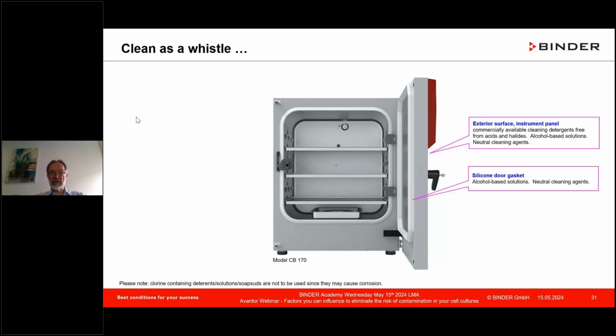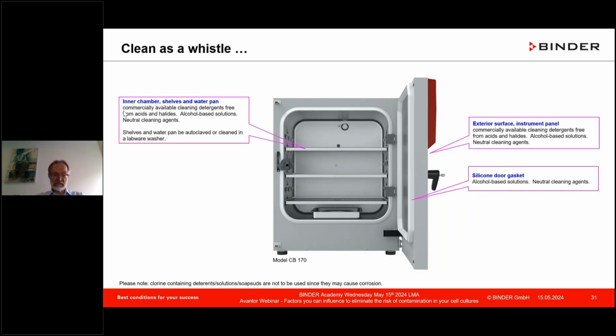The door sealing can also be removed from the door carefully, and you can clean that with 70% alcohol, for example. The inner chamber, the shelves you can take out, you can take the water pan out, the racks you can take out. They can be brought into an autoclave, or you can put that in your labware washer, depending upon the size of that washer, or you can go through the same process, wipe disinfection, detergents free of acids and halides. Always make sure of that, or you use or establish a routine including 70% alcohol.